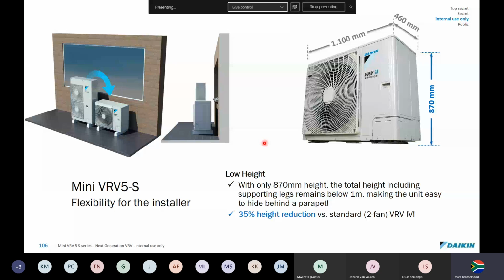It has a low height unit compared to the double fan, 870 high, which still makes it less than a meter, and there is a 35% height reduction when compared with a double fan. It's a little bit fatter, obviously, because the condenser coil curves more in to just maintain that same condensing capacity. They say lightweight, it still weighs 2 bags of cement, but it's 102 kilos, so it's definitely 2 men to carry it.